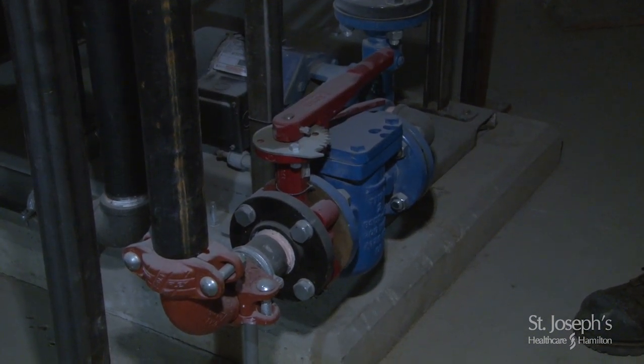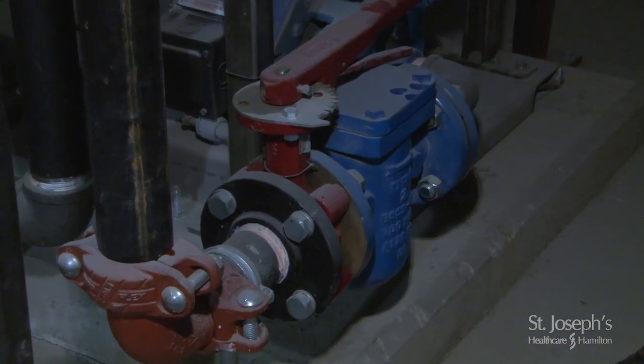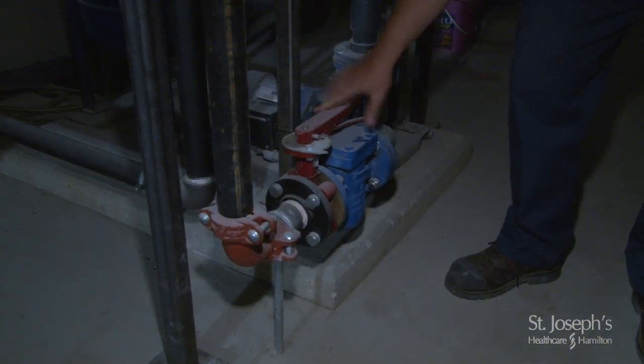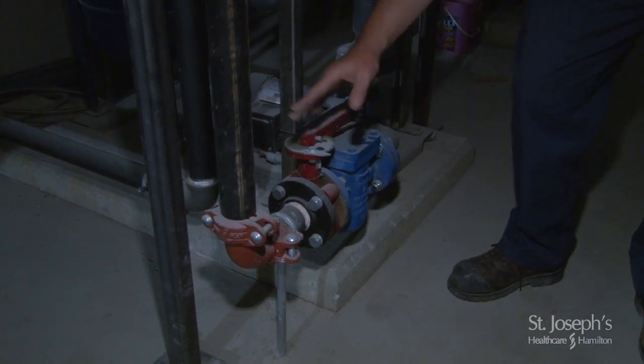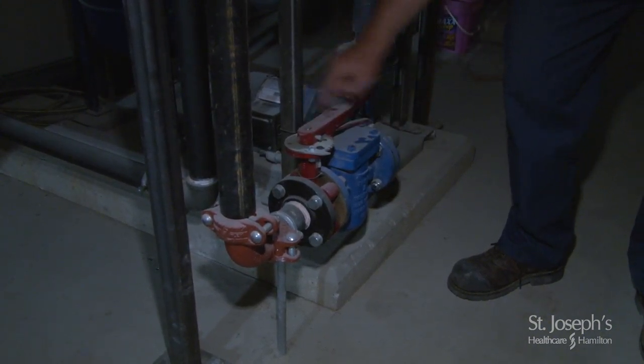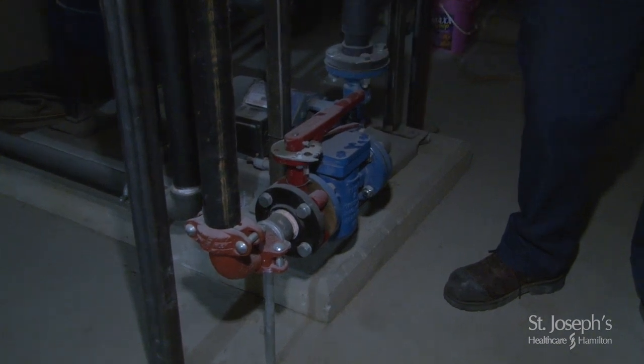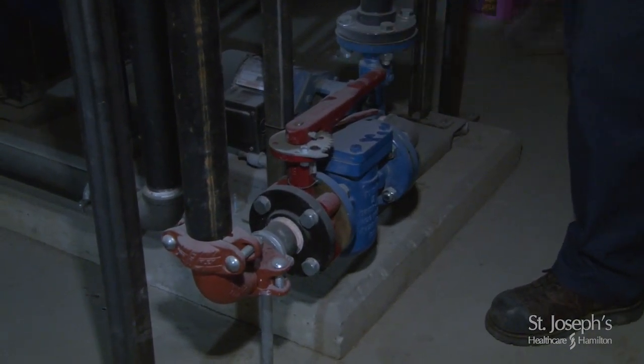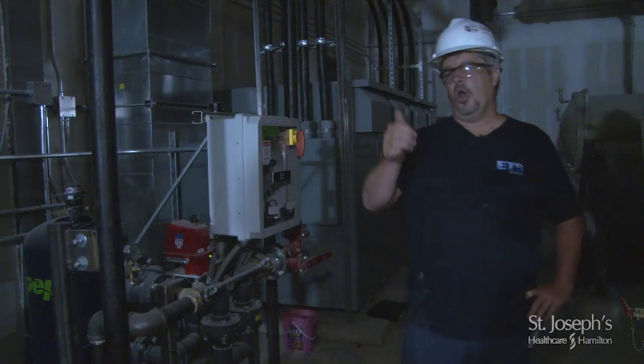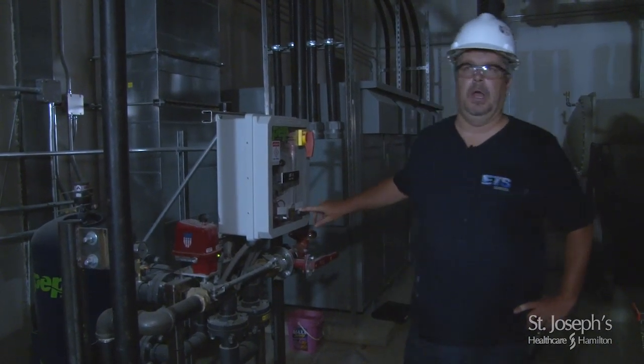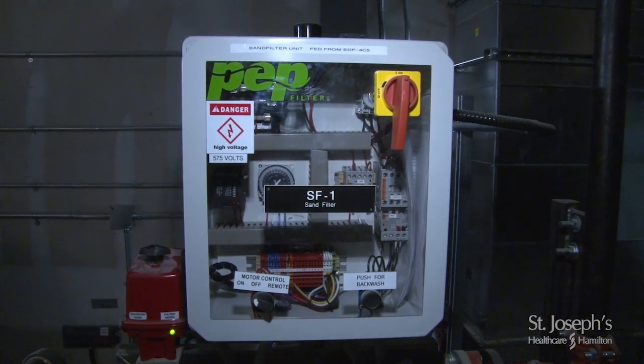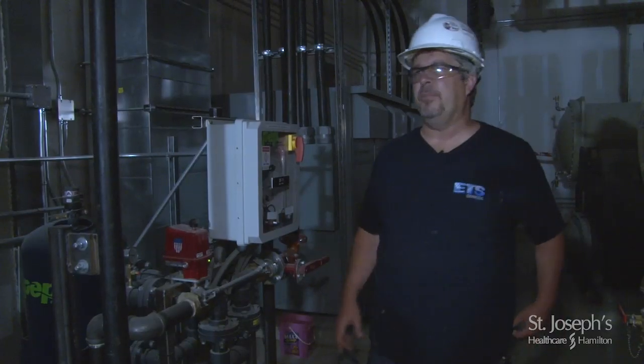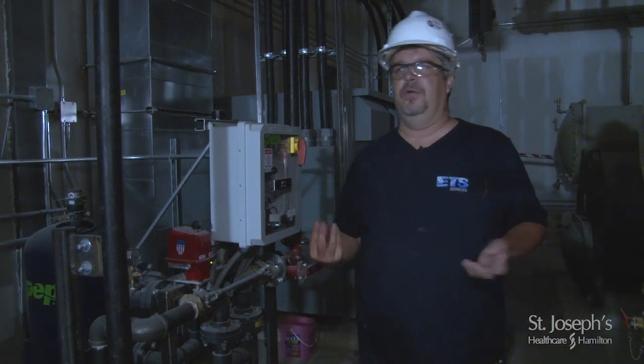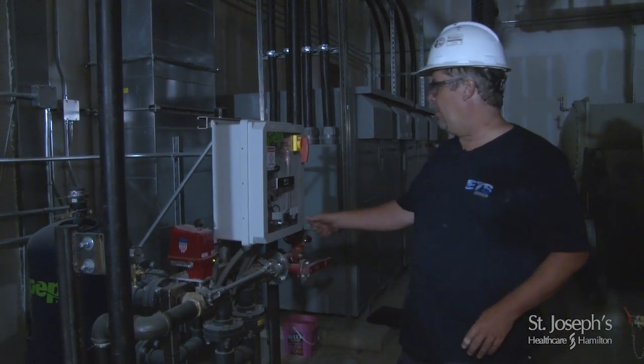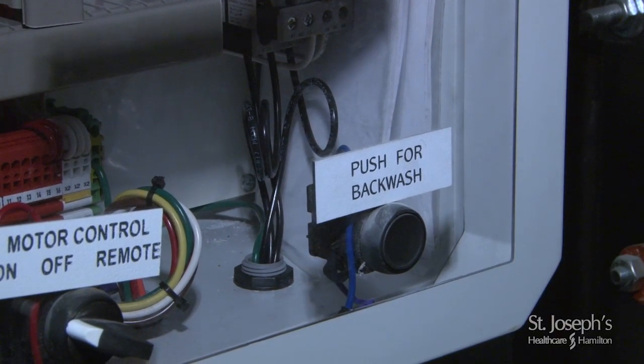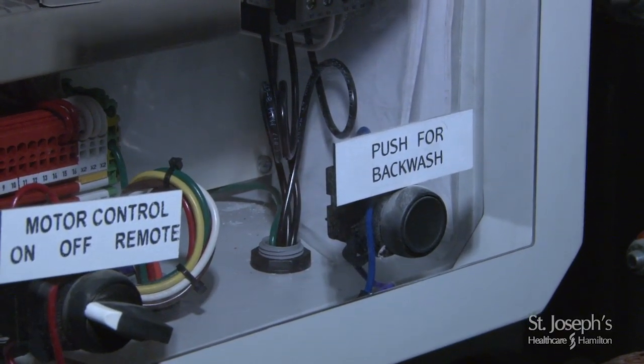The very first thing, if a unit is stuck in that loop of backwash and filter, is to shut things off, turn your valve to the off position to prevent the water from coming, take the 4 bolts off the top of this, remove the basket, clean it, reinstall, and put the unit back online again. You also have a maintenance button on the front of the panel. It's labeled push for backwash. That's where you as an operator, even though it's not ready to backwash, you could press this button and force the unit into a backwash cycle all on its own.